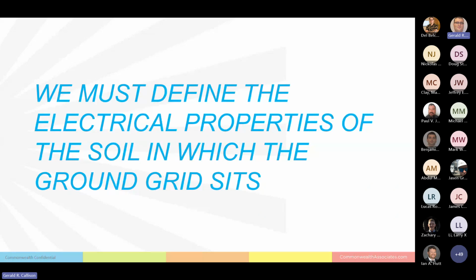Fundamentally what we're doing here is defining the electrical properties of the soil in which the ground grid sits. The ground grid is pushing ground fault current from the substation into the soil, back to its source. So we are defining the electrical properties of the soil into which the ground grid is pushing current. Everything we do with grounding depends on having a good soil model.